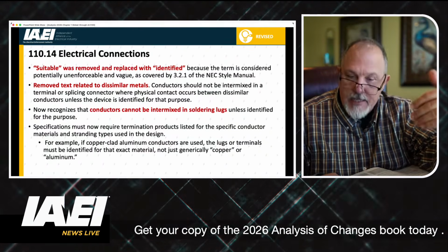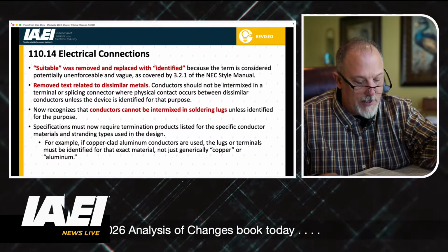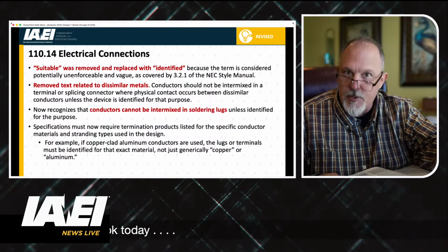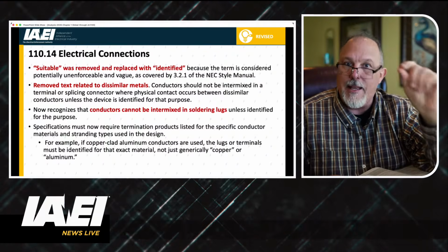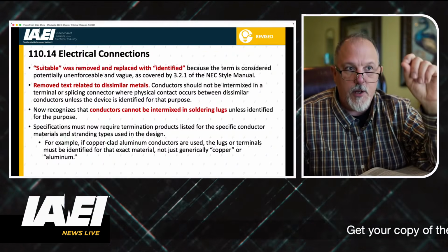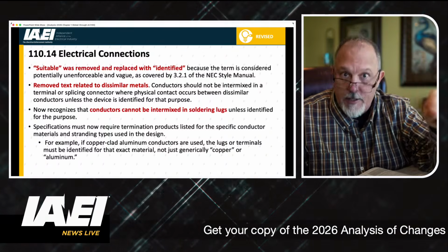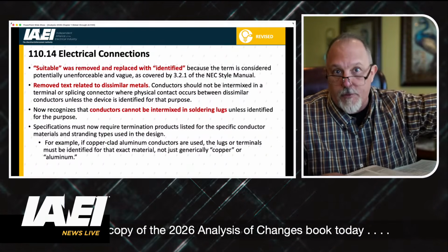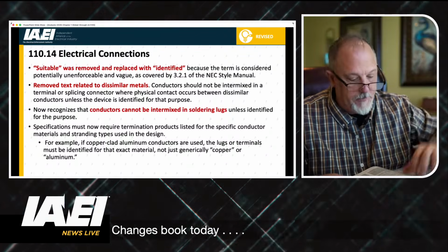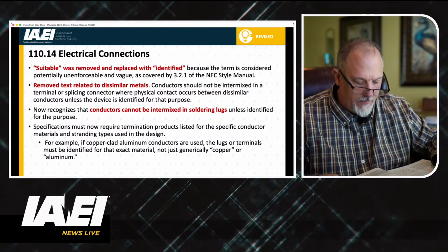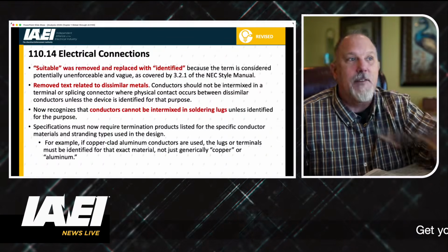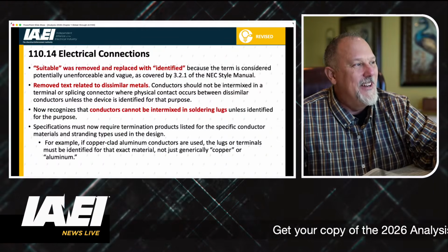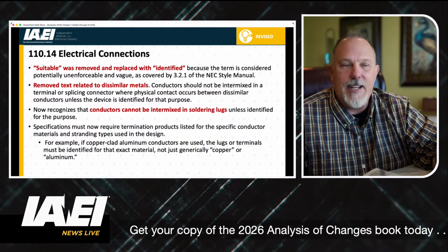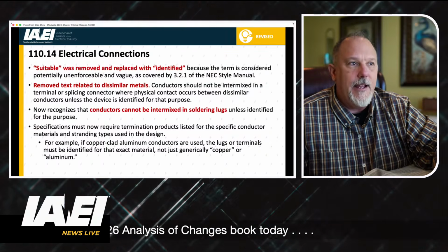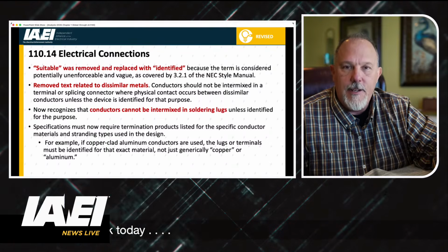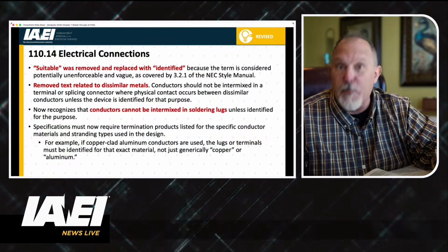Splices, that we talk about splices in B. C is the big one, which is your temperature limitations. That's where we limit the amount of current that you are permitted to pull through a termination, which then limits the amount of current that you can pull through a conductor, just because it's all a series circuit. And then D is your terminal connection torque values. Remember the torque. We went from just saying it has to be properly torqued, then to say it has to have a torque wrench, and then we said it had to have a calibrated torque wrench.